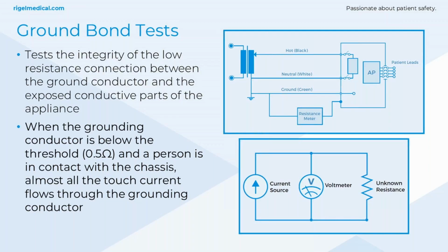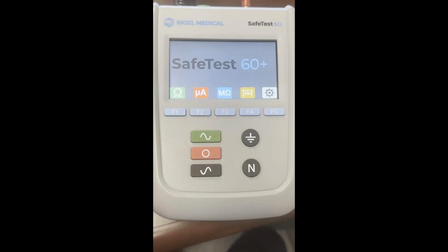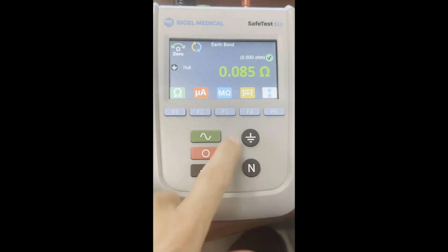Another means of safety is that we actually also measure that leakage current through the ground. And here is a quick demo video of the SafeTest in action with the limits on this particular test. Main screen, we hit the F1 button. From there we can see earth bond and the values are within spec. We zero the lead out first when we're connecting it to any medical equipment.